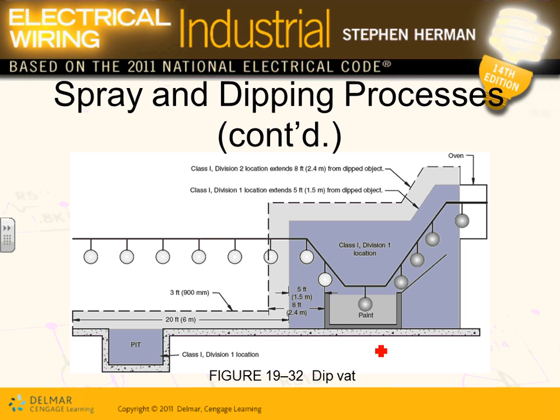This is exactly what we did when we went to Cummins. Do you guys remember all these pieces of the generator? They were moving on a conveyor and going inside the tank to be dipped. You remember that? They were getting inside the tank. This area is class 1 div 1. We have class 1 div 2, or class 1 div 1. Guys, when you paint, you have both hazards. You have dust and you also have flammable gases. So you can see the area up to 5 feet here, up to 8 feet here. All these are class 1 div 1, 3 feet off the ground right here, up to 20 feet away. Any pit is a class 1 div 1.